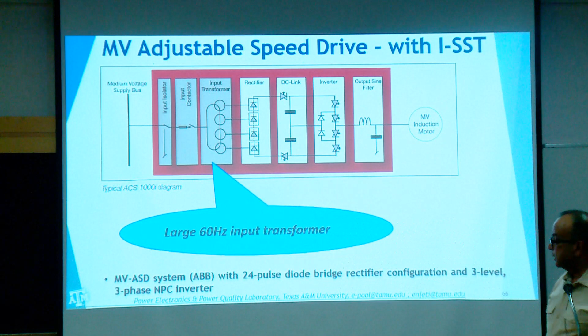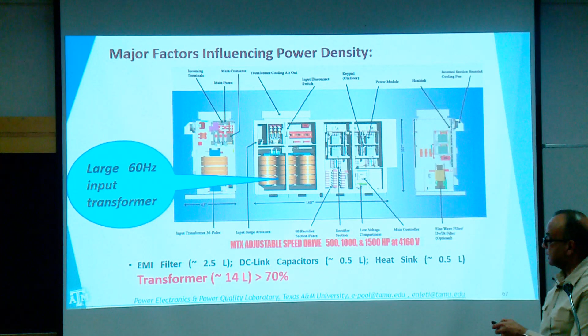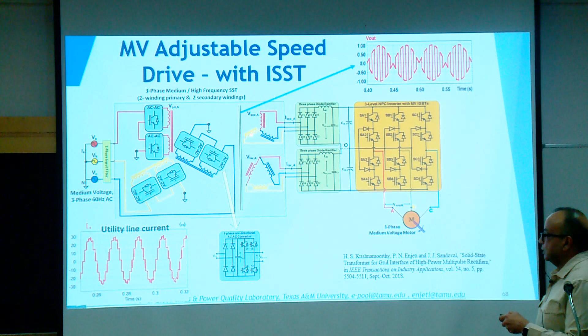And if you look at a medium voltage drive today, it has a lot of 60 hertz transformers and then the motor drive. So we work with Toshiba to make this into a medium frequency, they don't want a high frequency transformer, they want a transformer around 1 kilohertz or 600 hertz, to reduce the size to 1/3. There we have an AC-AC converter, standard star and delta, and this side is the same. So again, a medium voltage drive, which has a 60 hertz transformer, 11 kV coming in, and there are so many transformers here.